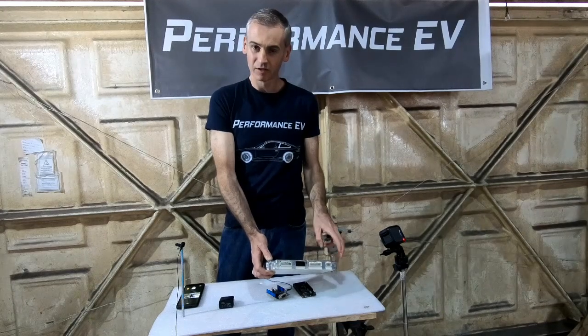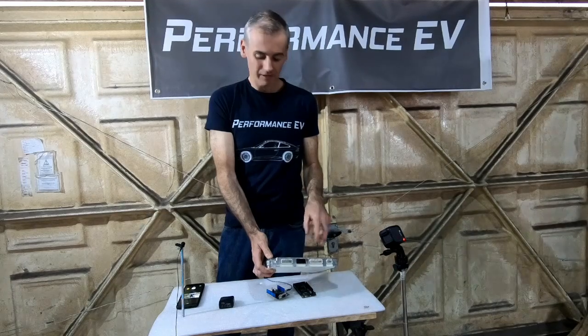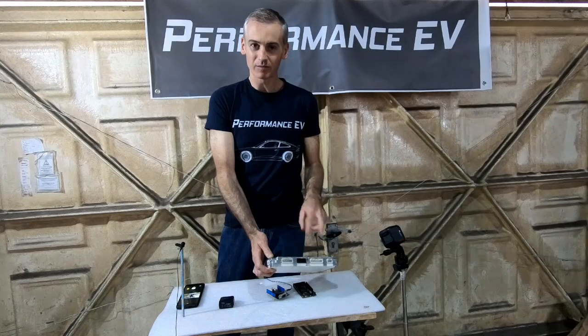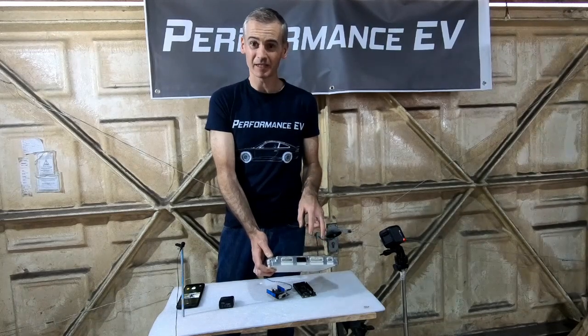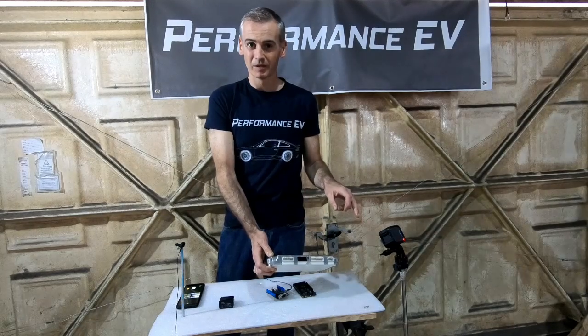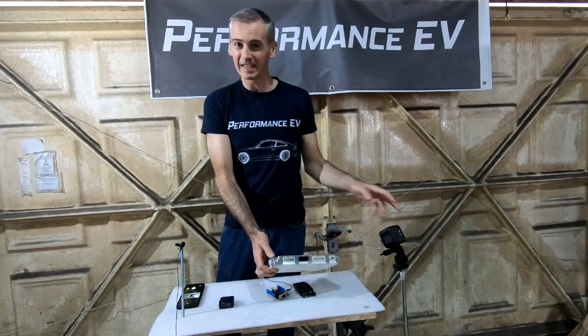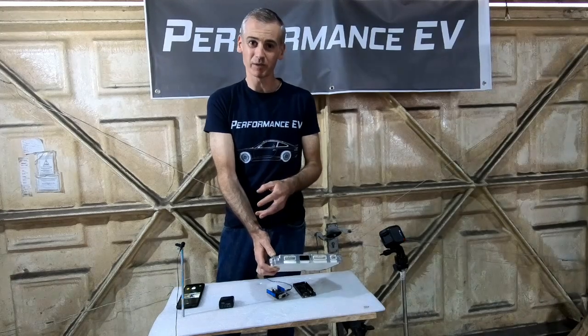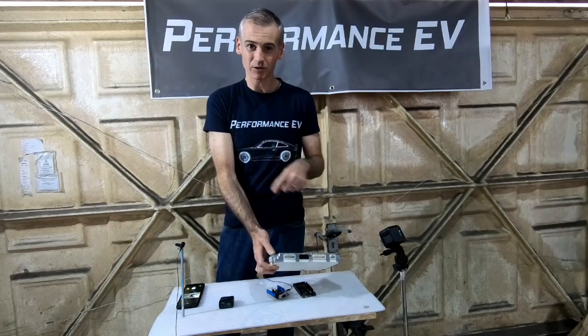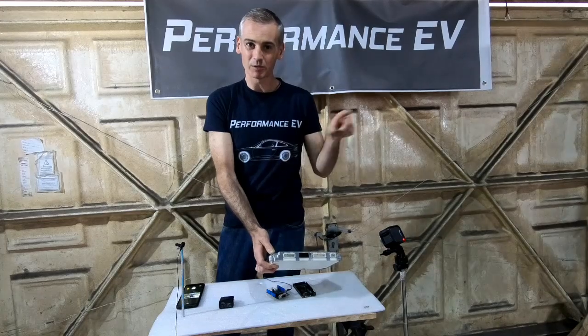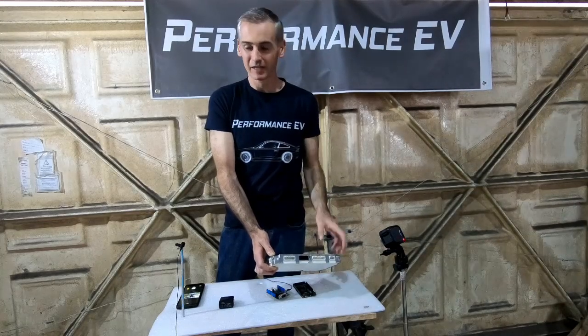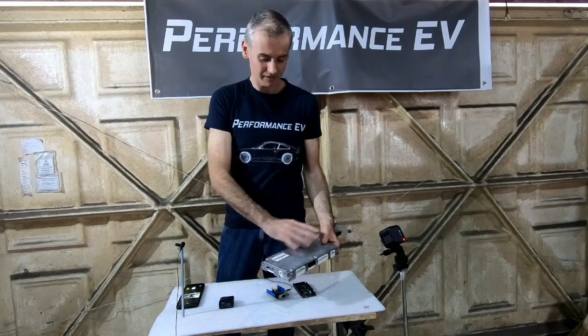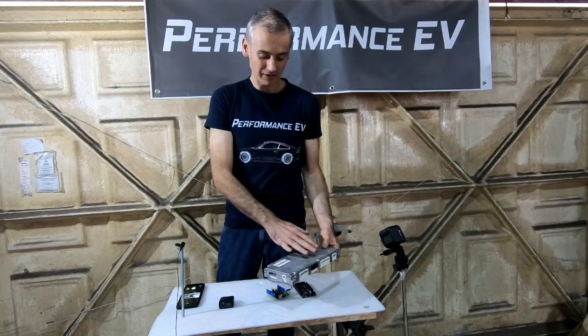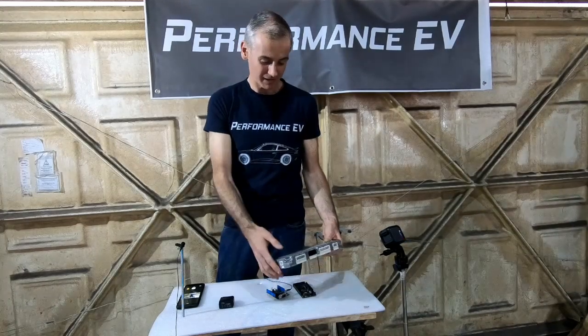But if you get it wired up wrong, or if they've changed a pin or two, then instead of reading the value from the same cell, or even two cells that are close together, you could actually be taking a positive from one cell and then a negative from a cell that's 3 or 4 modules away. All of a sudden, because you've wired up the battery, the voltage between those two points is much higher, and that can fry the more delicate electronics they've got in here, which is used to help you read the signal.